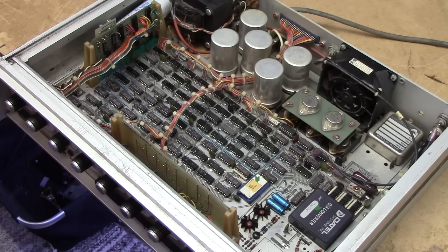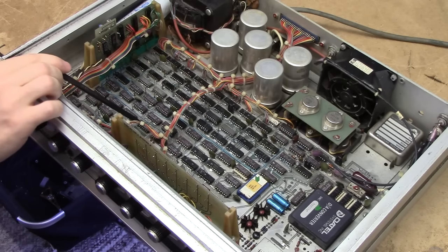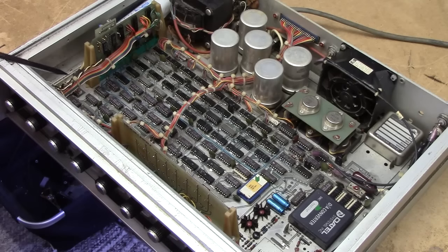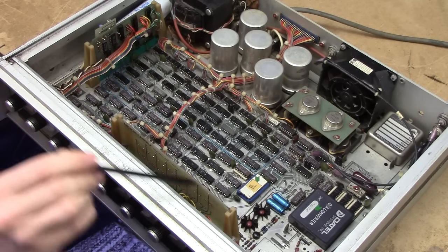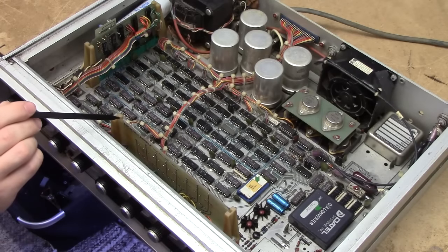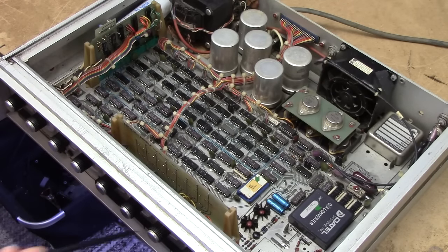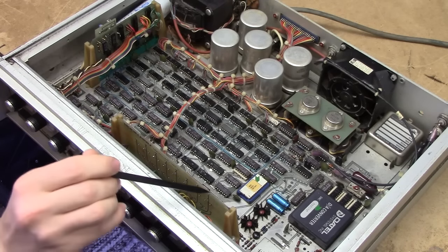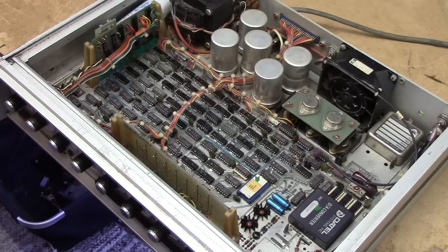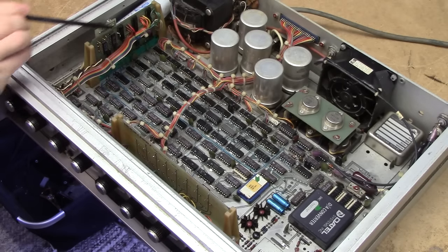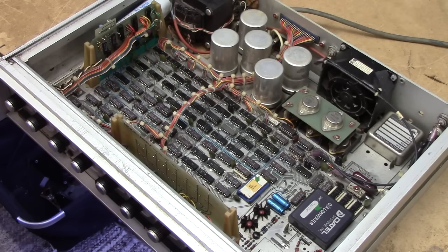However, I will go through the general build of this unit in a very mechanical sense. So it's obviously got a three board construction with this mainboard down here housing the major array of circuits. In the front here we have an attenuator board which is controlled by the attenuator buttons in the front. It's just a heap of resistors on the backside of it, which you can't really see. And over here to the left we have the front panel scanning board, which basically makes up the difference between this and the model 5110, which was the same thing except without the front panel controls.